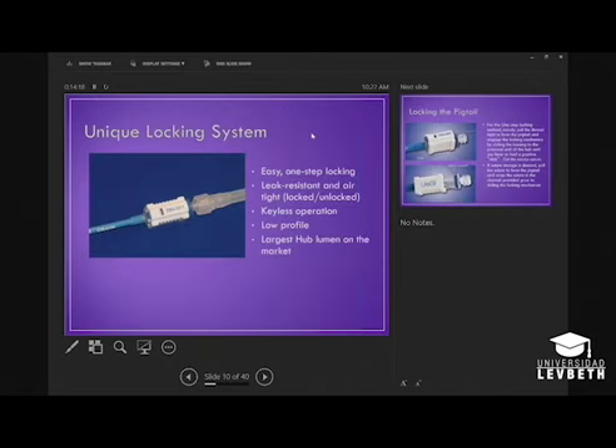So here's the hub. This is an older picture. Now our catheters have a clear hub, it's not white, and they have a black sleeve instead of that blue sleeve where it says drain. That's blue, this is now black, and the catheter hub is clear. So this is locked right now. Like I said, it's air seal tight, it has a low profile, it has the largest inner lumen on the market. Right where that blue sleeve is, you can see the increase before it gets inside the white part, where it increases to the 16 French that allows for the flow and doesn't allow occlusion.